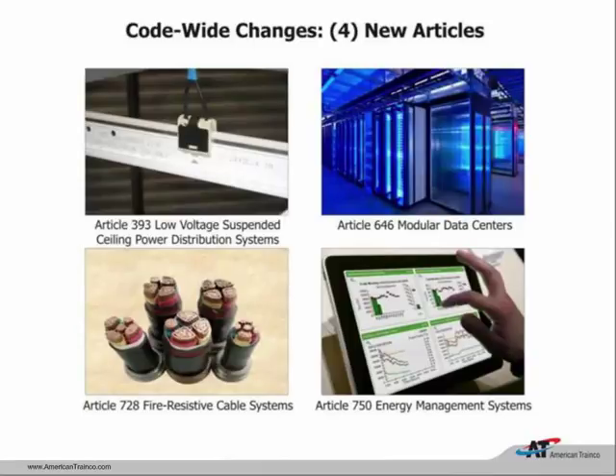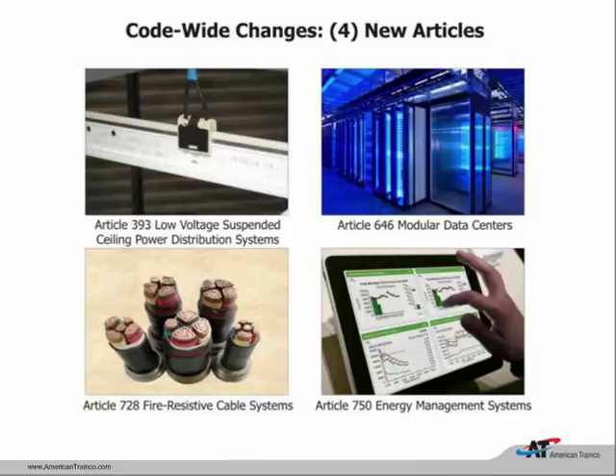There are four brand-new articles in the 2014 National Electrical Code. The first is in Chapter 3, Article 393: a suspended ceiling system that will conduct electricity, powered by a Class 2 low-voltage power system—probably around 24 volts, and it can be DC. My question is always: who's going to install this—the ceiling people, or will electricians be putting this ceiling grid up? We'll get better pictures when we get up into wiring methods.